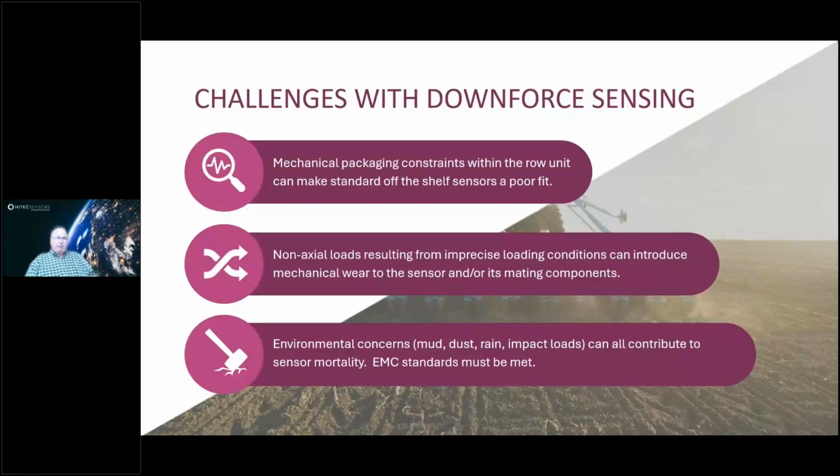Another thing that occurs in the downforce sensing application is the potential for non-axial loads to be witnessed by the load cell, due to mechanical tolerances, stack up and interference fits with various components. There is certainly the possibility of introducing extraneous loads to the sensor, which can cause mechanical wear and or destroy the sensor or its mating components. So you basically need to adjust for that and accommodate that in your design.